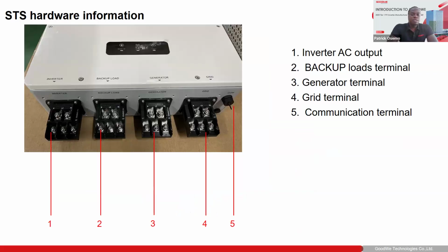The 50 kilowatt hybrid needs to be connected to this static transfer switch. You can see port number 1 is the inverter AC, so the inverter power will be connected here. Then we have other ports. We have the backup port, which is for the critical loads. We have the generator port, to which you can connect a generator. We have the grid port, in which you can connect the incoming grid line.